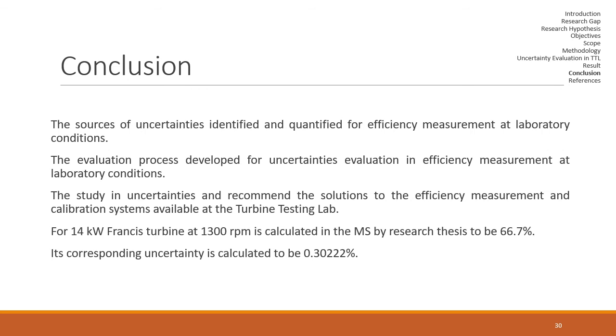The efficiency of 14 kW Francis turbine at 1300 rpm is calculated in the MS research thesis to be 66.7%, and its corresponding uncertainty is calculated to be 0.30222%. As we already discussed, the value of uncertainty required to meet IEC standard is less than 0.2%. Although the result obtained is close to IEC standard, the Turbine Testing Lab needs to work on standardization more to meet the IEC standards.